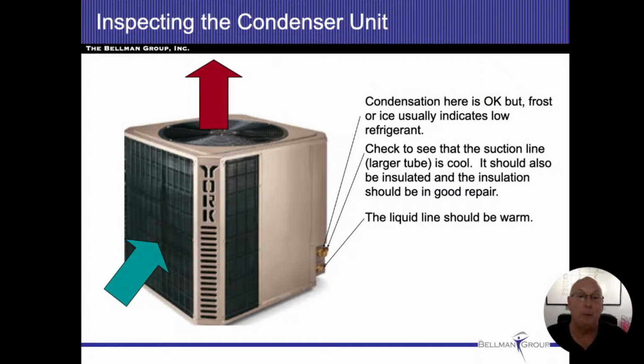However, if I'm losing refrigerant and I don't have enough in the system, then that pipe is already going to be much colder than the 50 degrees. It's going to be below freezing. When it gets below freezing, any condensation that forms on that pipe is going to freeze with it. And then you end up seeing this big ball of ice on the suction line. That's a pretty strong indicator that we're low on refrigerant.